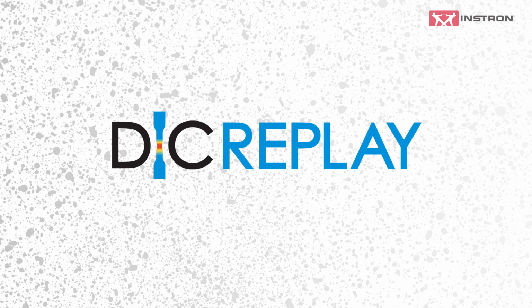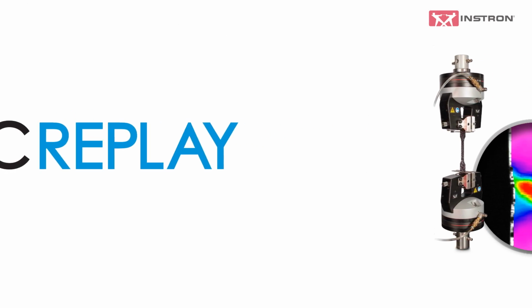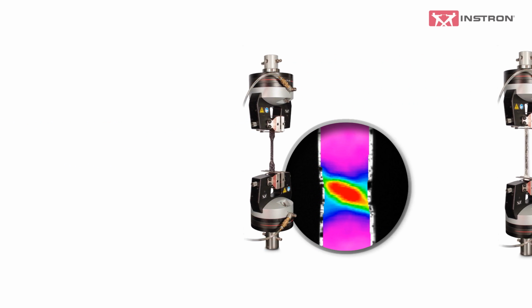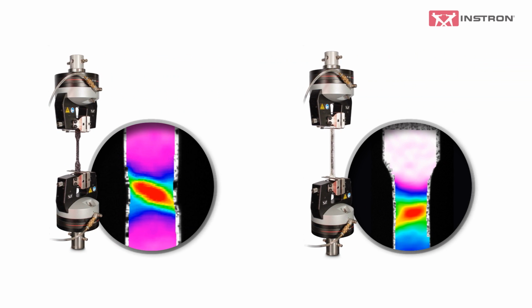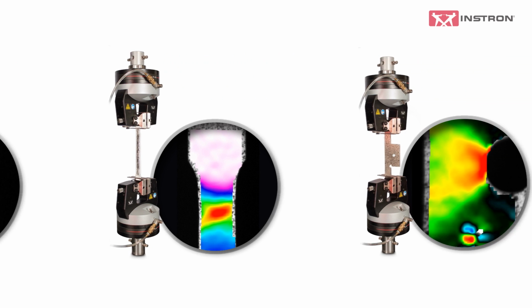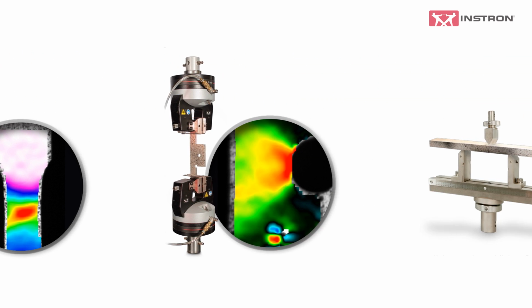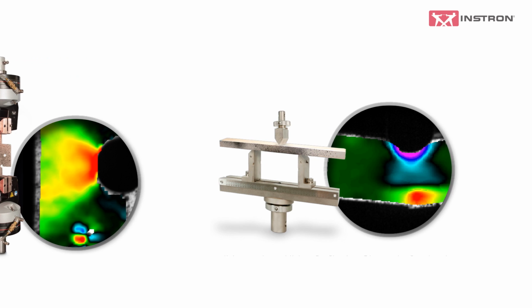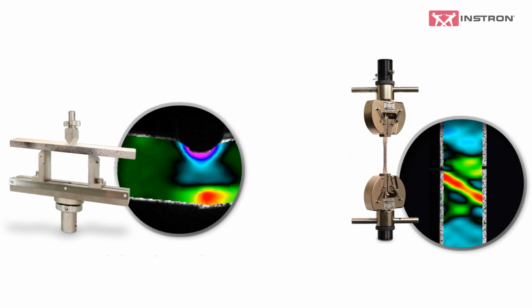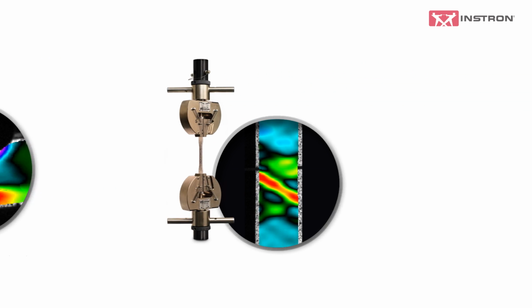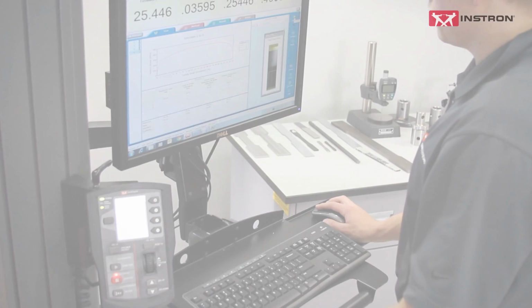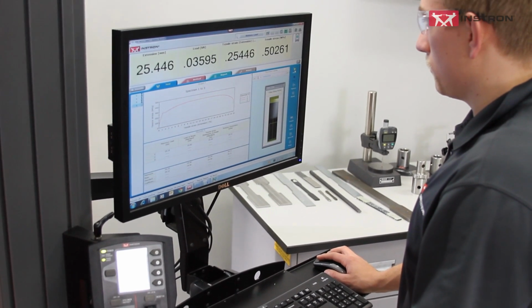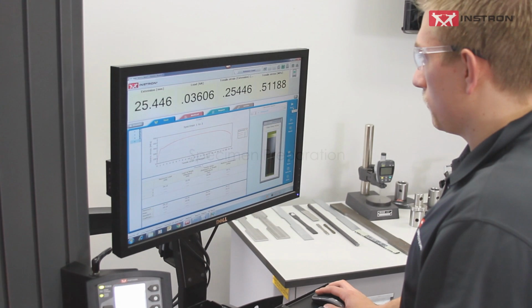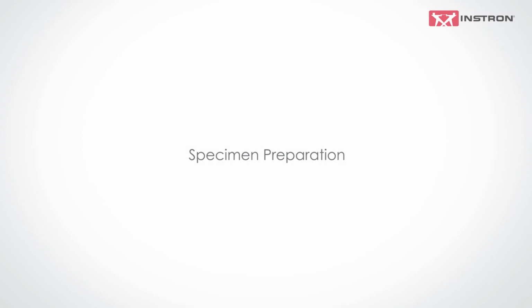Digital image correlation, or DIC, is an optical technique that compares images of a test specimen's surface to generate full field strain and displacement maps. In other words, users can visualize strain and displacement over the full two-dimensional surface of the test specimen. This powerful capability unlocks the true story of the material behavior and allows materials testing professionals to analyze a number of advanced strain characteristics after the test is complete.